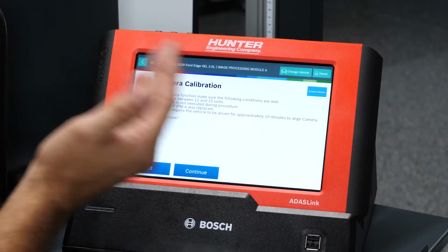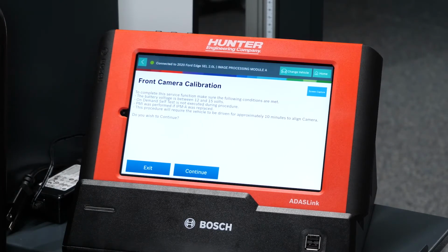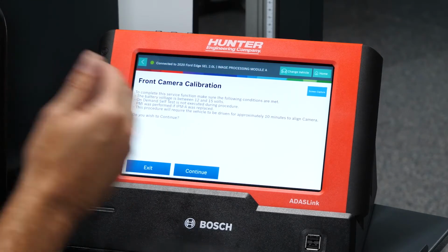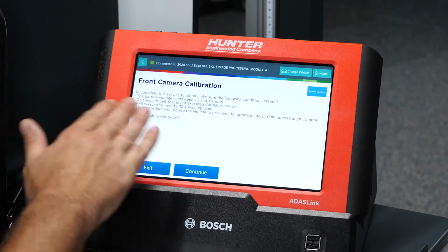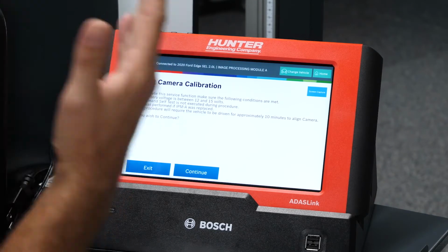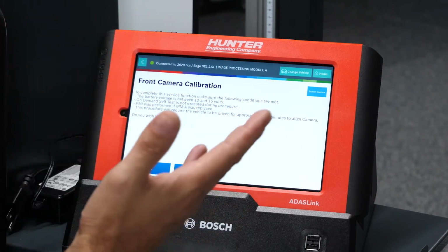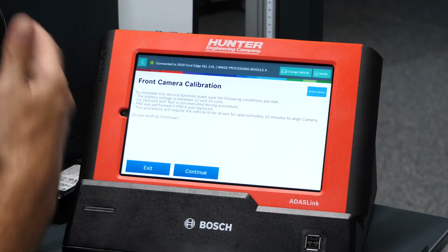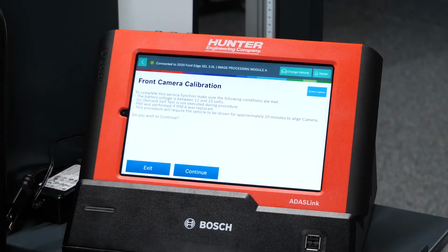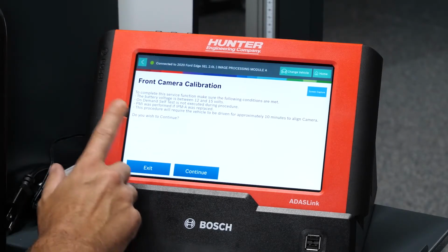Battery voltage between 12 and 15. Self-test is not executed during the procedure. PMI was performed if it was replaced, which we did not replace the module. They went ahead and reused the original camera, which is absolutely fine. Again, it just needs to be recalibrated once it's been moved on there. Do you wish to continue?